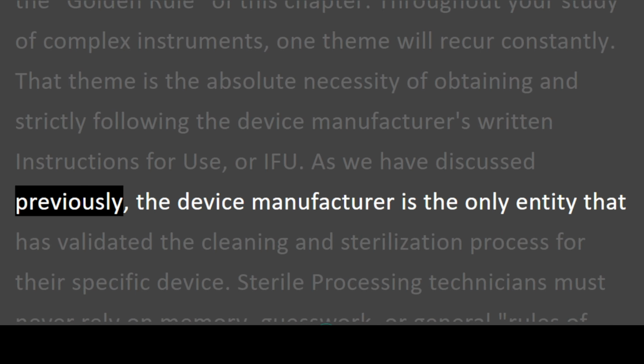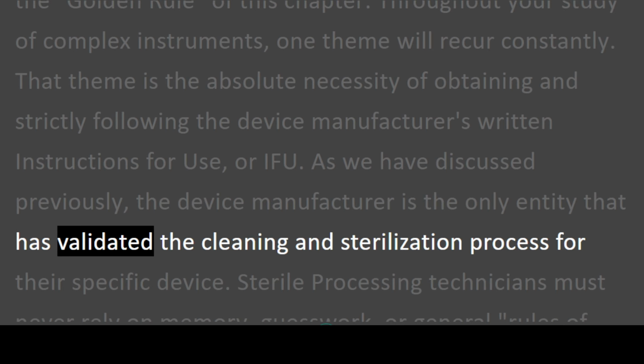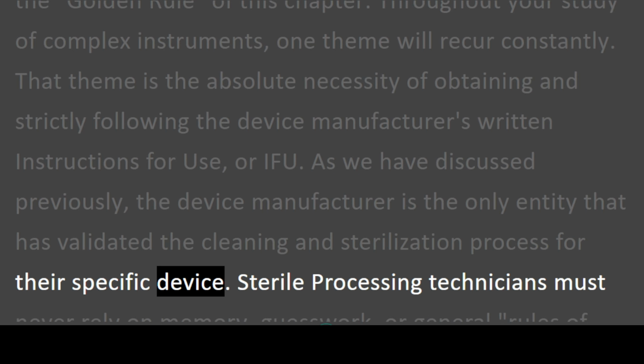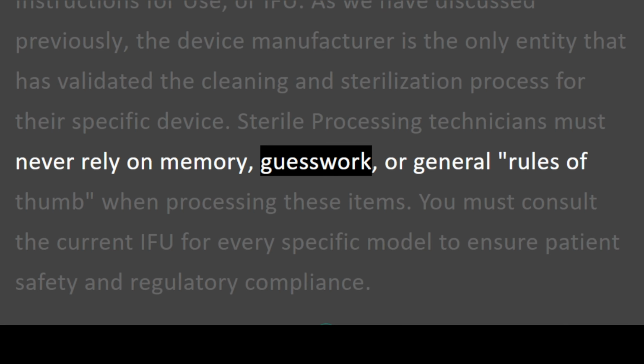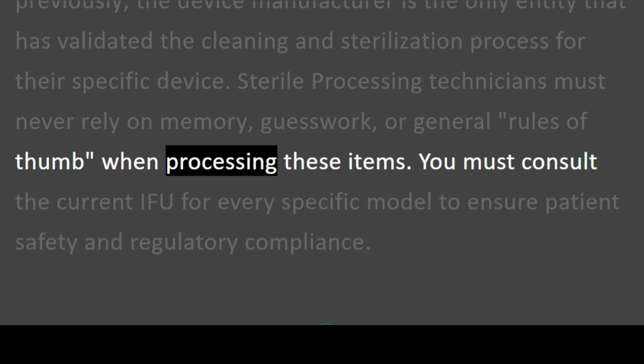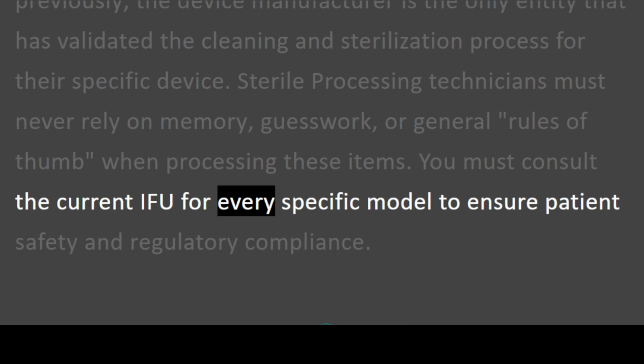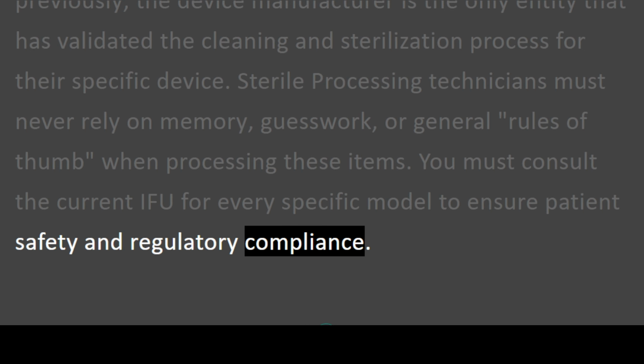As we have discussed previously, the device manufacturer is the only entity that has validated the cleaning and sterilization process for their specific device. Sterile processing technicians must never rely on memory, guesswork, or general rules of thumb when processing these items. You must consult the current IFU for every specific model to ensure patient safety and regulatory compliance.